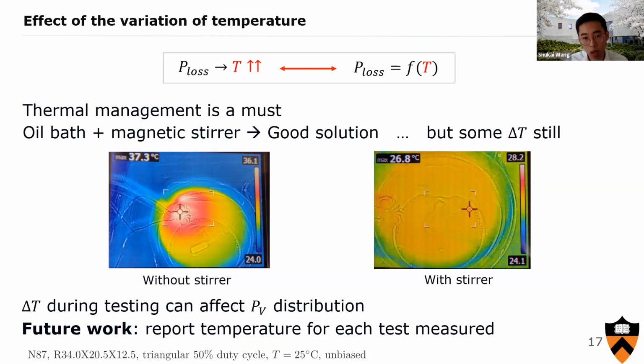So one of the solutions that we had was to add a magnetic stirrer. And with that, as seen on the right side here, we're able to keep the oil temperature relatively low and make sure the oil distributes that heat out into the rest of the tank, so that we don't have a hot spot in one specific spot. This is especially important because temperature can vary your core losses significantly. Just 1 or 2 degrees can cause errors. But the problem is, for our system right now, we're able to keep this temperature as close to what we wanted as we can.